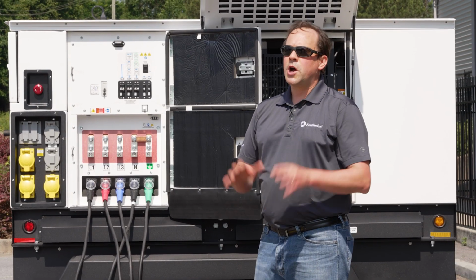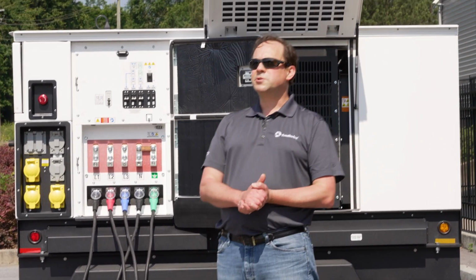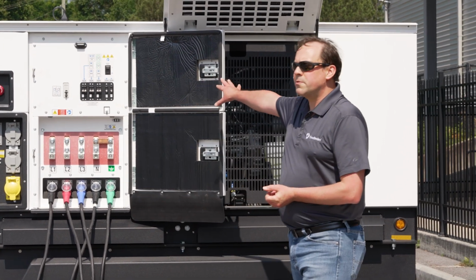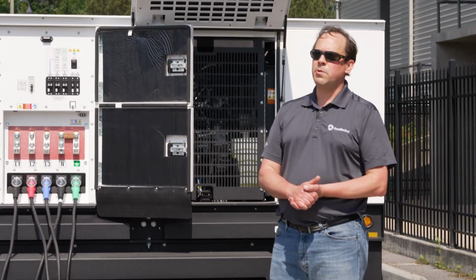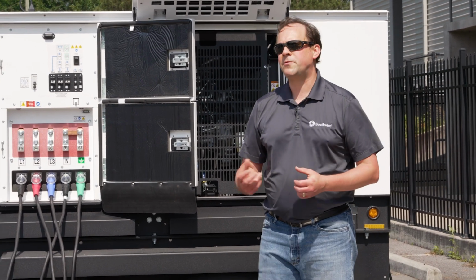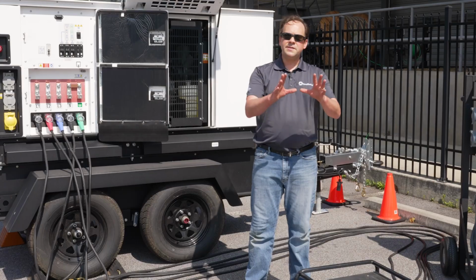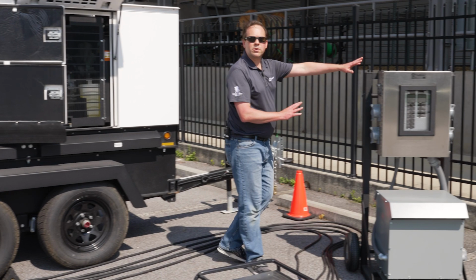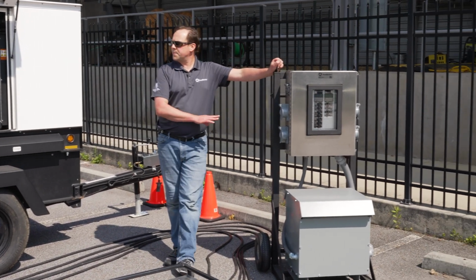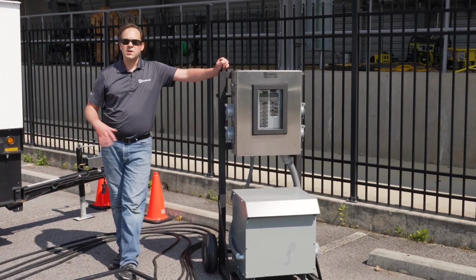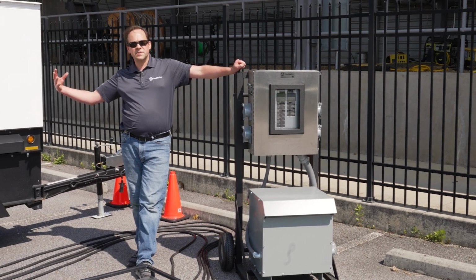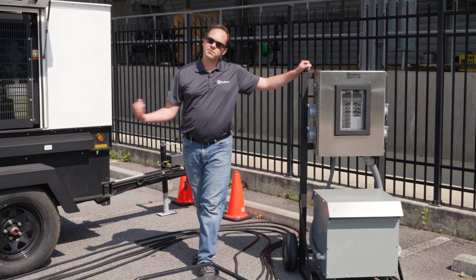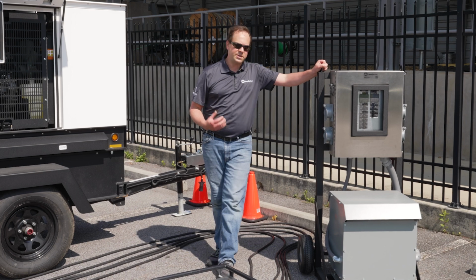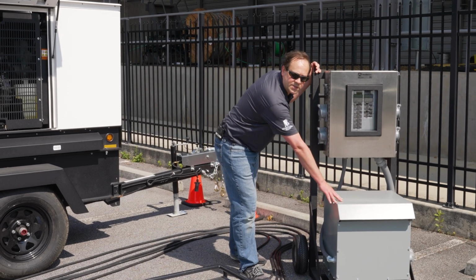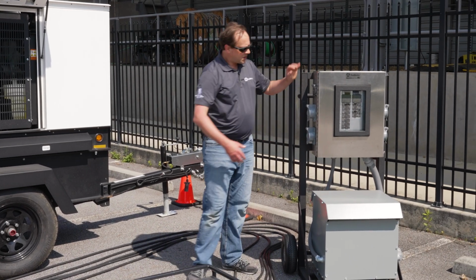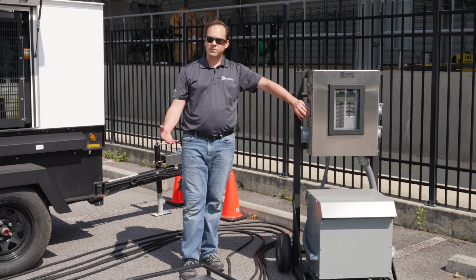Now, lastly, on your largest commercial and industrial jobs, you might not find your generators running at 120/208 volts. You might find them running at a higher voltage, 480. In this case, this is where our temporary power carts come in. What our temporary power carts enable a user to do is take that higher amperage service and that higher voltage service, usually again at 480, but it could be 600, and step that down via a transformer to something you can use. In this case, a 120/208 volt service.